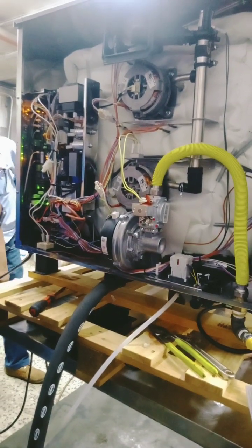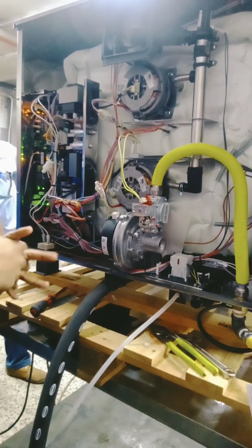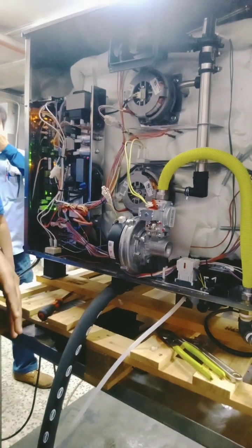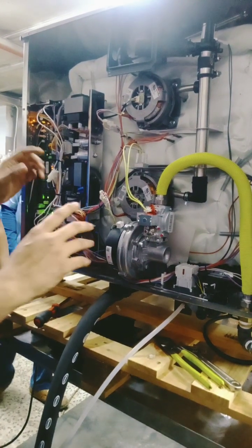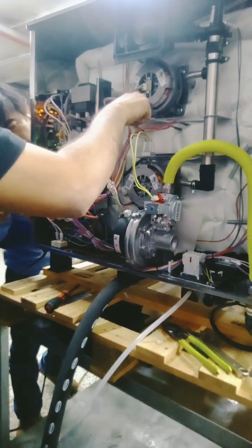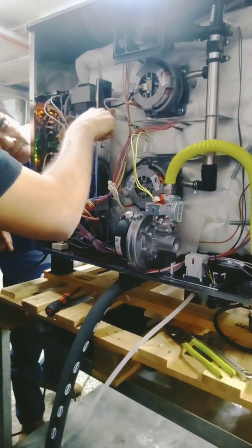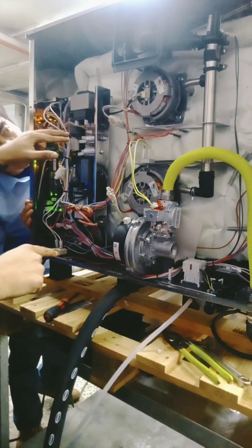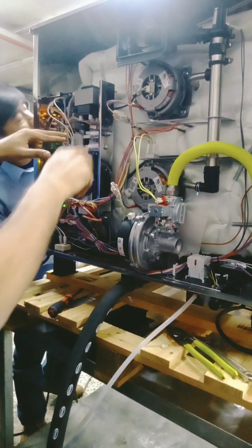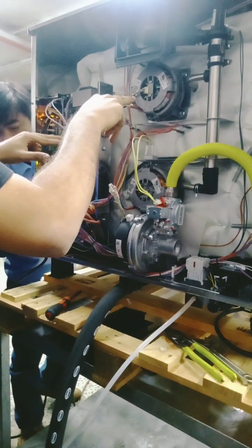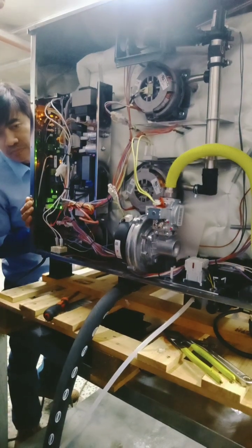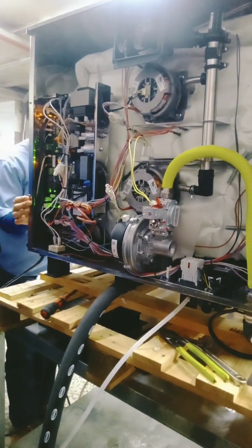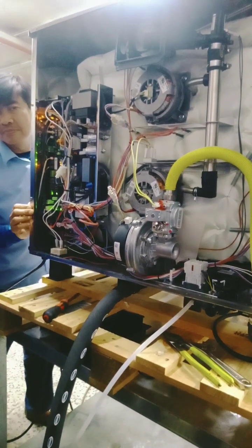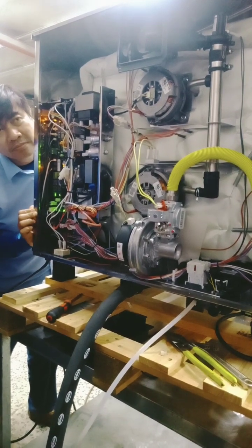I don't have any issue for too much, because the error for this one is just common. Very common, yes. For all ovens, same. AF01, motor: check the continuity, and whether the capacitors are weak, or the motor is stuck, a mechanical block. But if the thermal sensor for this motor is gone but the motor is still okay, you need to advise to change the motor.